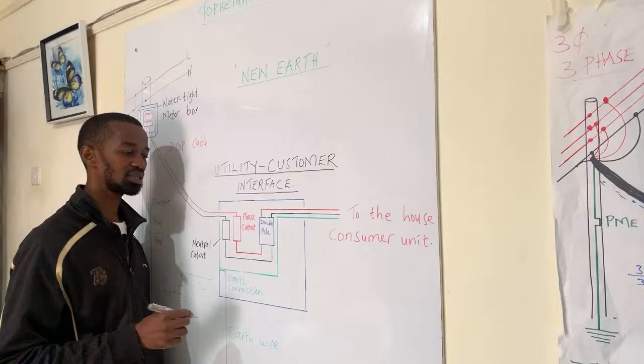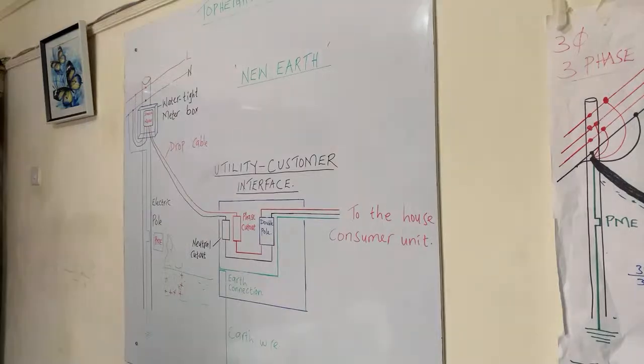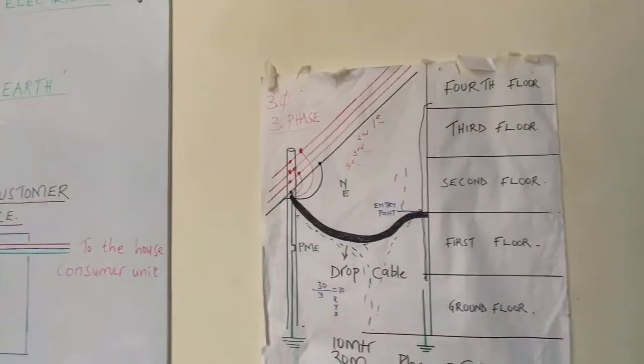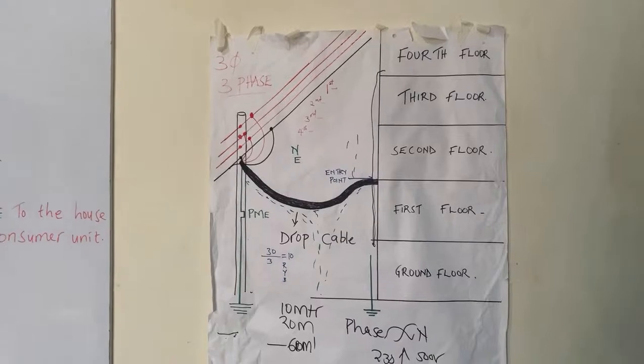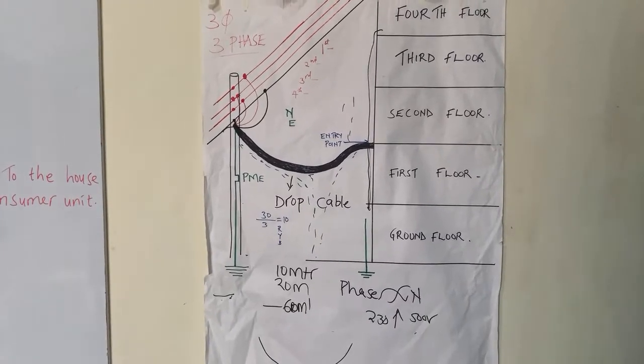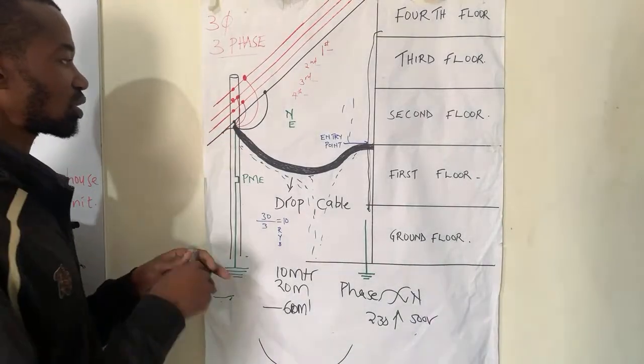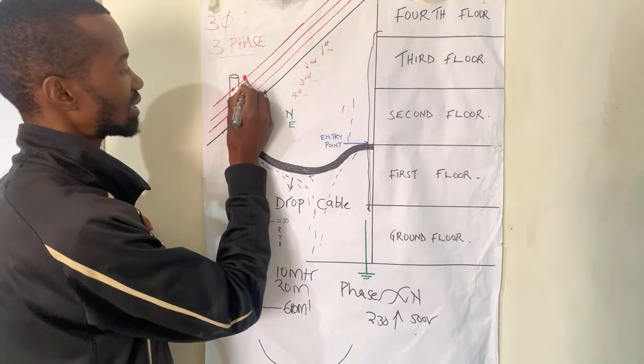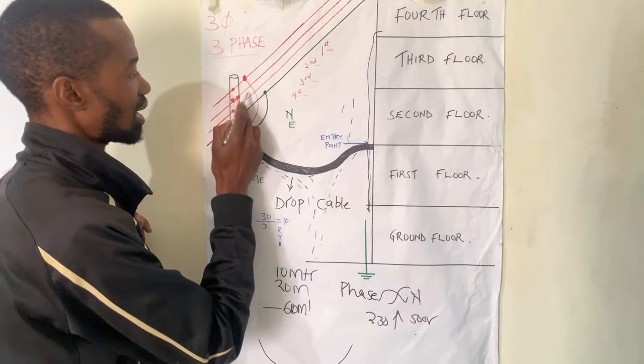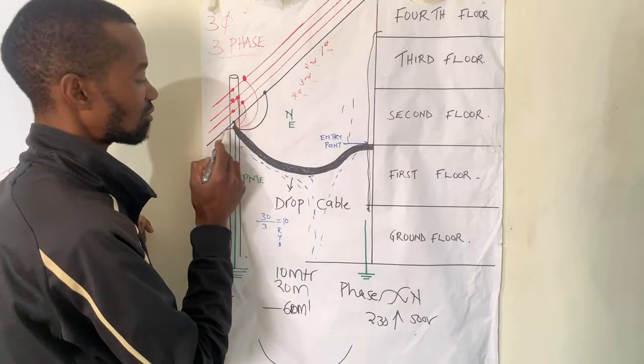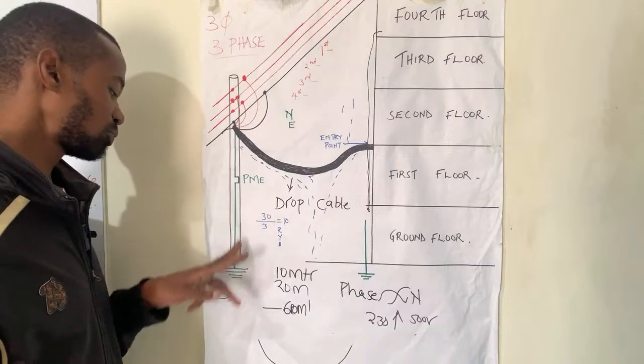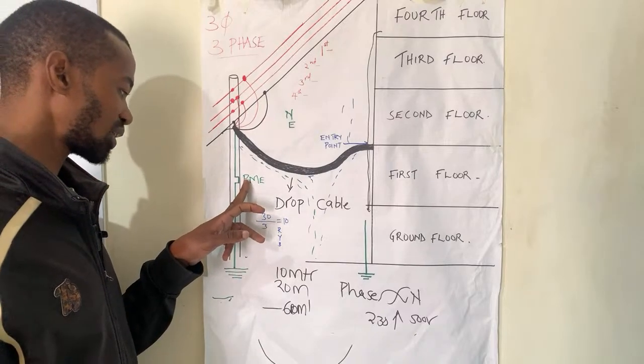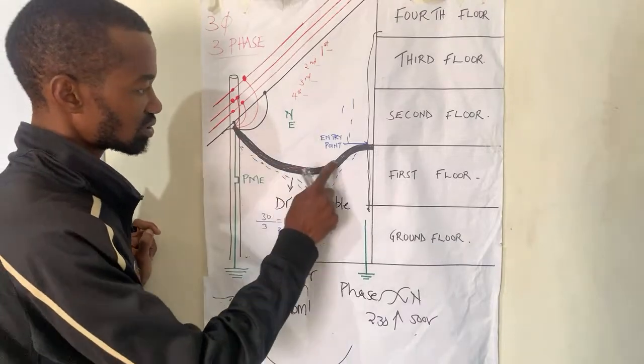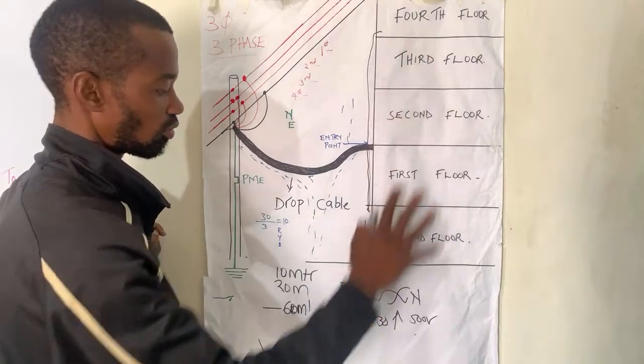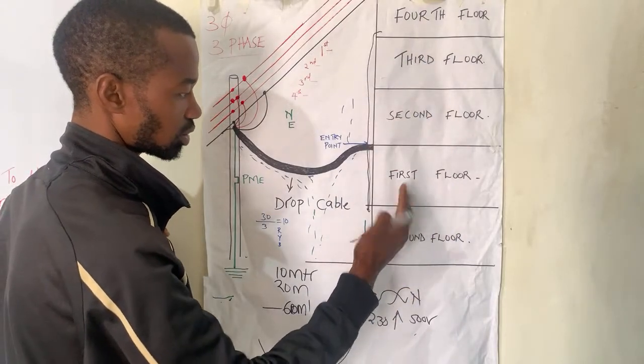If you are talking about a three-phase, or if you're talking about an industrial setup, or if you are talking about this particular point here, it is very important for you to also take note that this three-phase connection, we have the phase, the first one, conductor, which is a red phase, a yellow phase, and a blue phase. This is a return for our case here, which is also looped to the ground through this protective multiple earthing. So you'll have these three phase drop cable to serve the whole of this apartment.